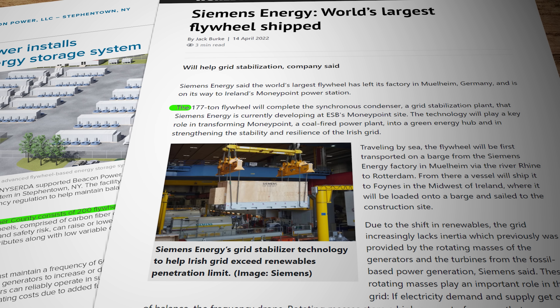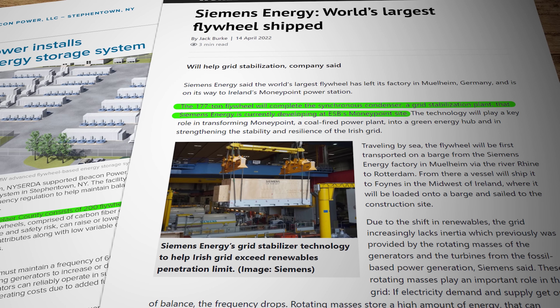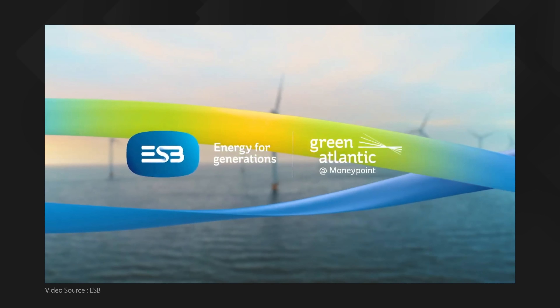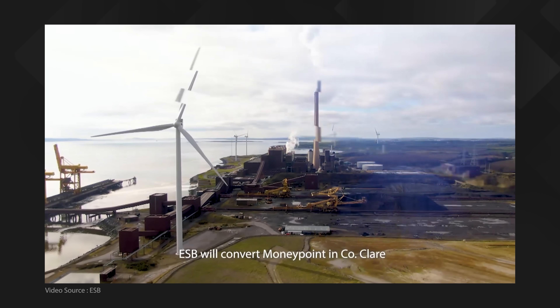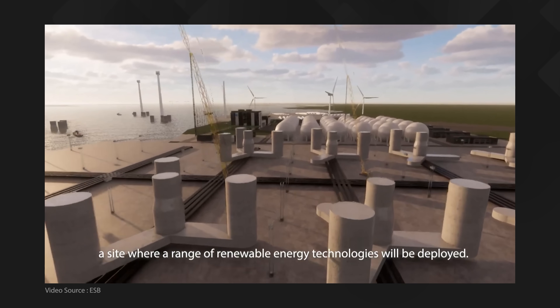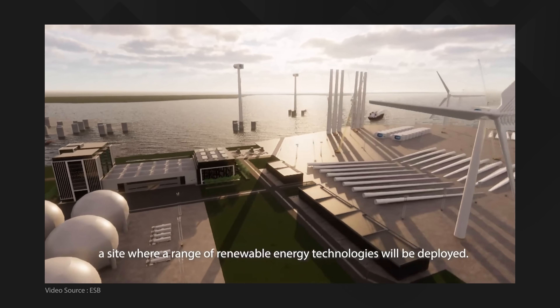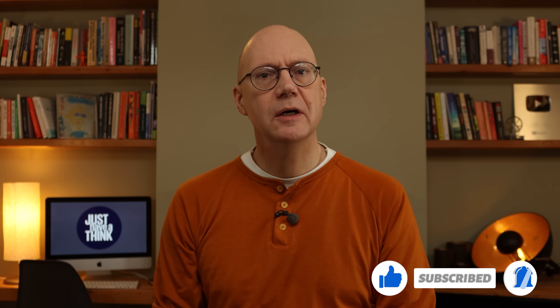In April 2022, the German technology giant Siemens completed production of the world's largest single flywheel — a 177-ton behemoth that'll be installed at the Moneypoint power plant in County Clare in Ireland. It's part of an ambitious project by Irish energy company ESB to transform Moneypoint from a dirty coal-fired facility into a renewable energy hub, with floating offshore wind and green hydrogen production and storage that'll have the capacity to power 1.6 million Irish homes. The flywheel, or synchronous compensator as it's more technically known, will be capable of providing 4,000 megawatt-seconds of inertia — twice as much as the current Moneypoint plant turbines can produce.